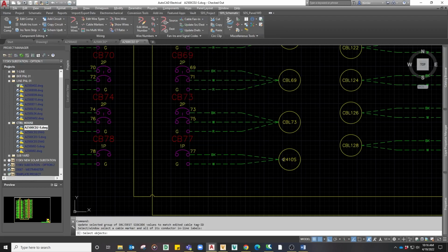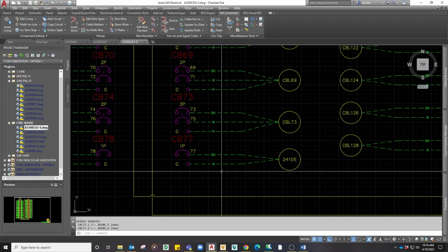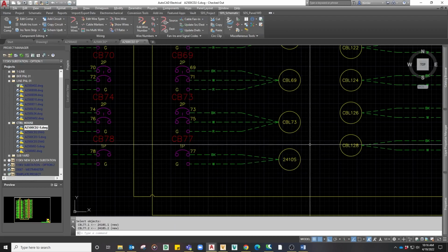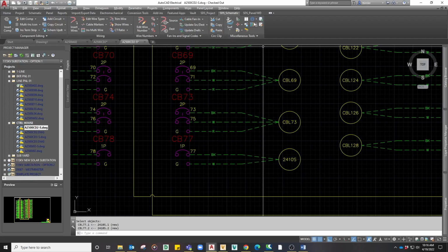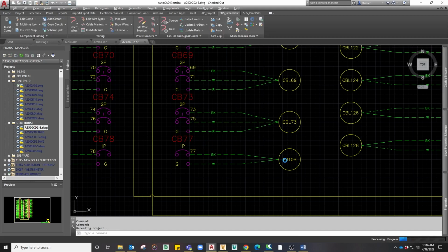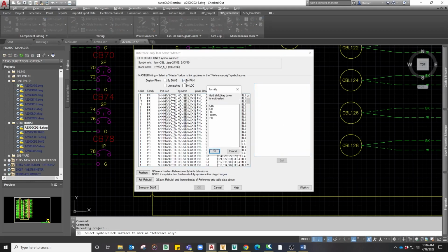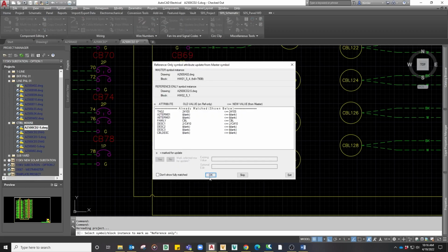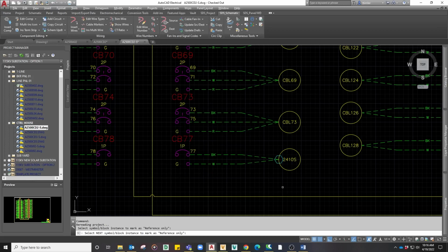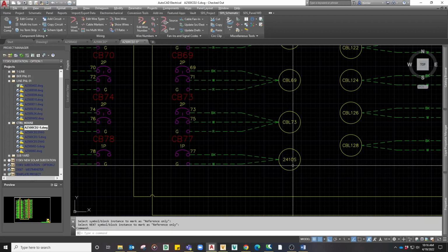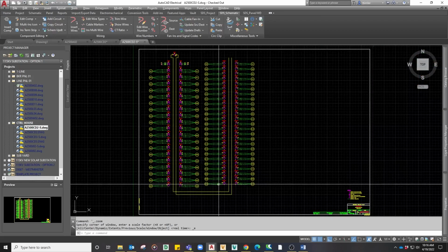Select cable SIG code update, select the bubble. Now this end of the cable is matching the other end, completing the cable run. Before I leave the drawing, I'll again have to make sure that I reference this symbol back to the parent master using the SDS ref only tool in order to get the deref cross-referencing I need. This step will obviously become obsolete if this gets corrected in the tool. Now I can save and move on to my AC distribution panel connection diagram.